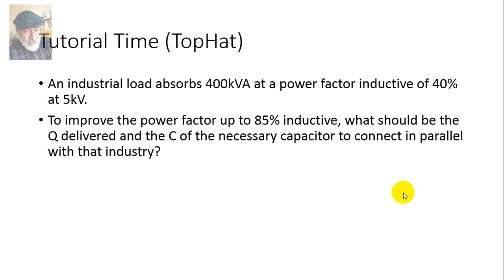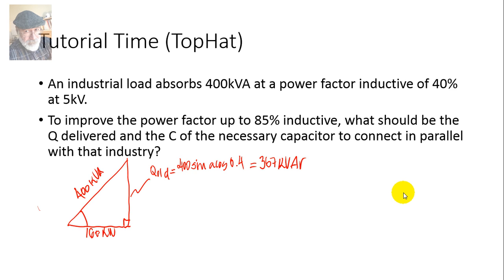P cannot change, because P has to do with the actual useful work done by the factory. So check this out: 400 kVA of apparent power is the hypotenuse of the power triangle. The triangle is right side up because the power factor is inductive, 40%, so the cosine of this angle is 0.4. The hypotenuse is 400, so this is 400 times 0.4, which is 160 kilowatts.